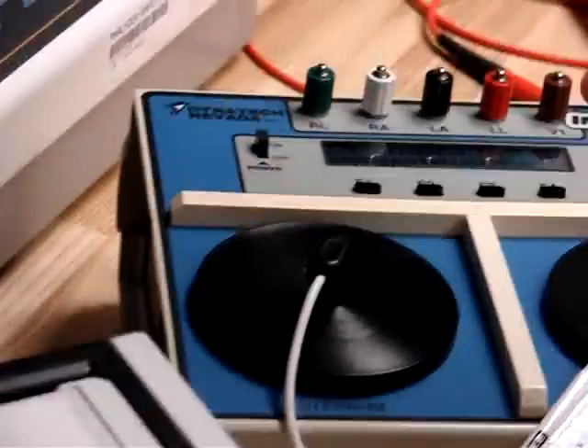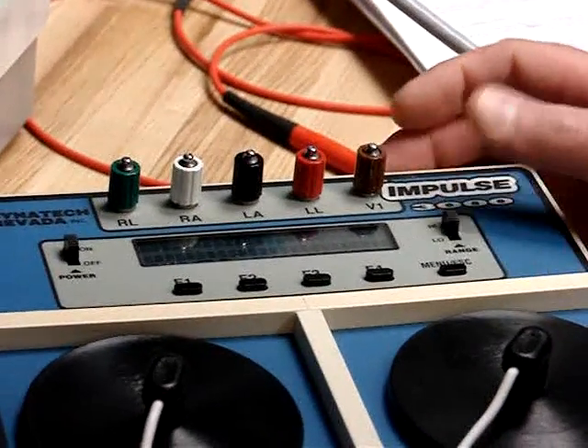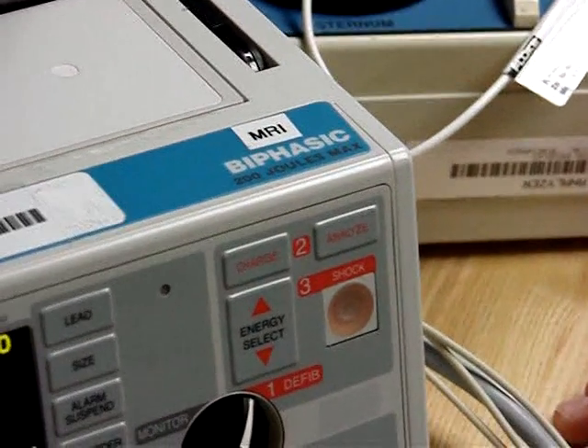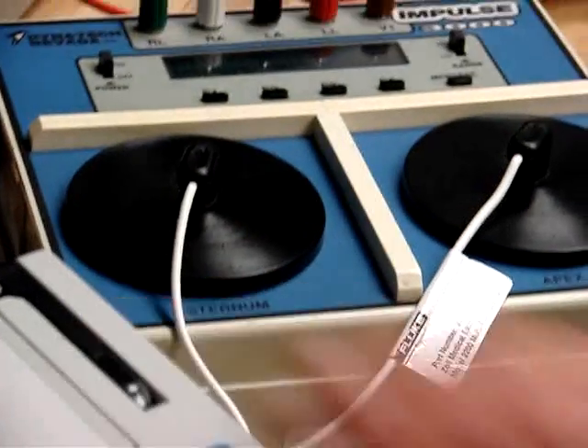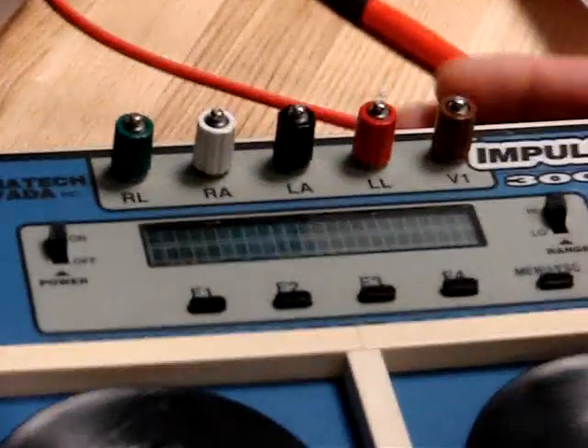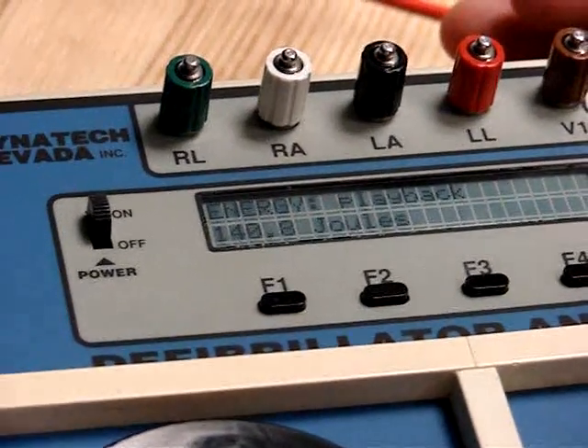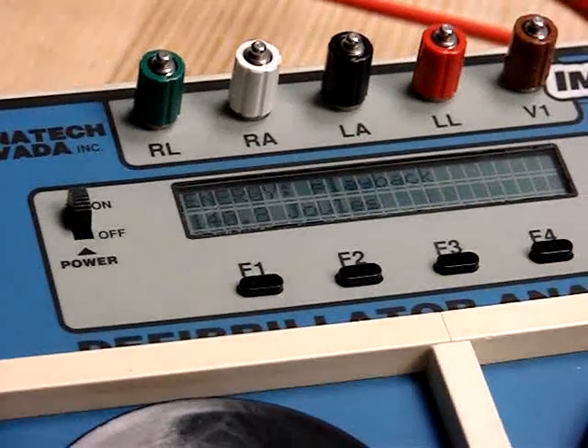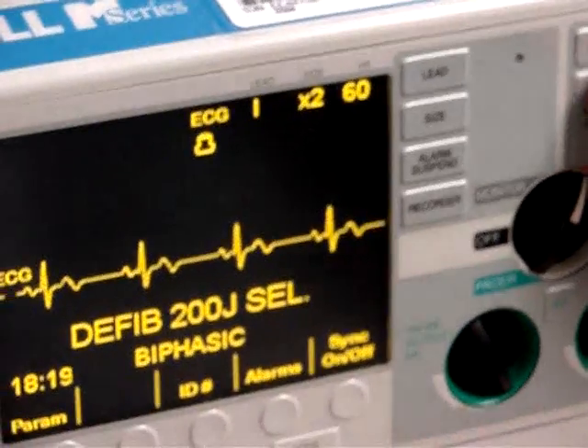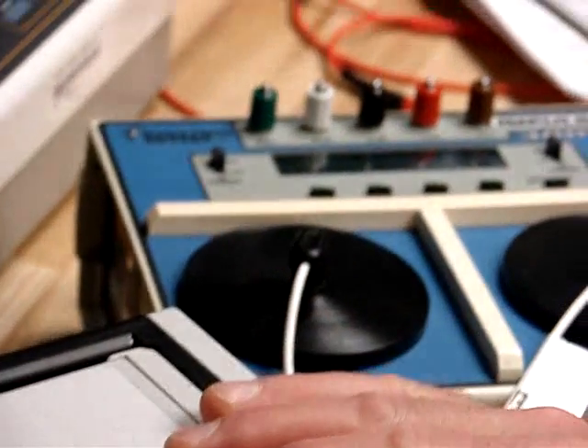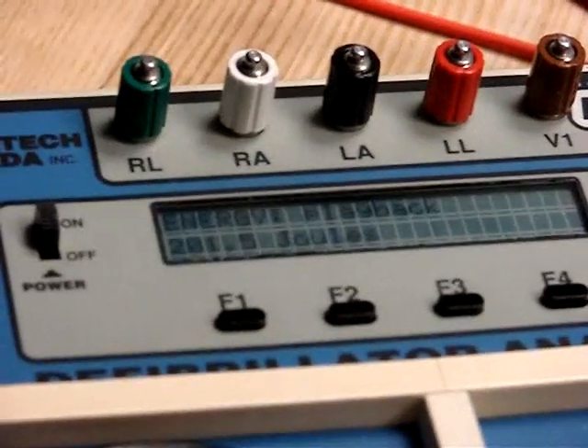We'll take our range switch up to high now because we're over 100 joules. We're going to charge. As soon as we reach 150, we'll discharge the shock. We'll check our reading. We have 140.8 joules. That's well within 15%. Now we'll adjust it up to the max setting, which would be 200 joules. We'll charge it. When we reach 200 joules, we'll shock. Check our reading of 201.5 joules, well within the plus or minus 15% range.